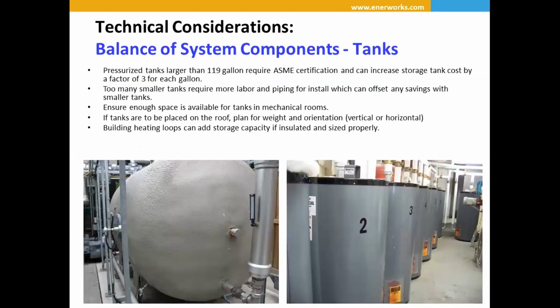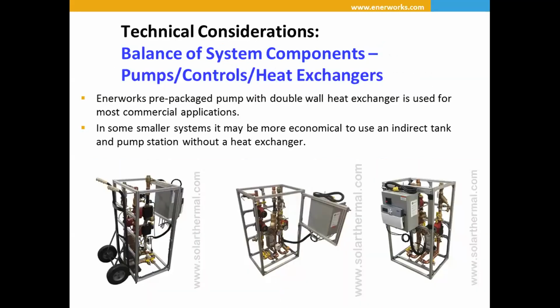Storage tanks is another very important one. I'm actually going to go back. There's been a number of systems, and we can talk about this later, a number of systems where the design of the pump station has been put outside on the roof. And I just want to be clear, I'm not aware of any manufacturer that makes the pump station to go on the roof exposed. Ours is actually designed to be in a conditioned space. The limitation here is actually the controller on the front of the unit. It can't go below freezing, and it can't go above 100 degrees.